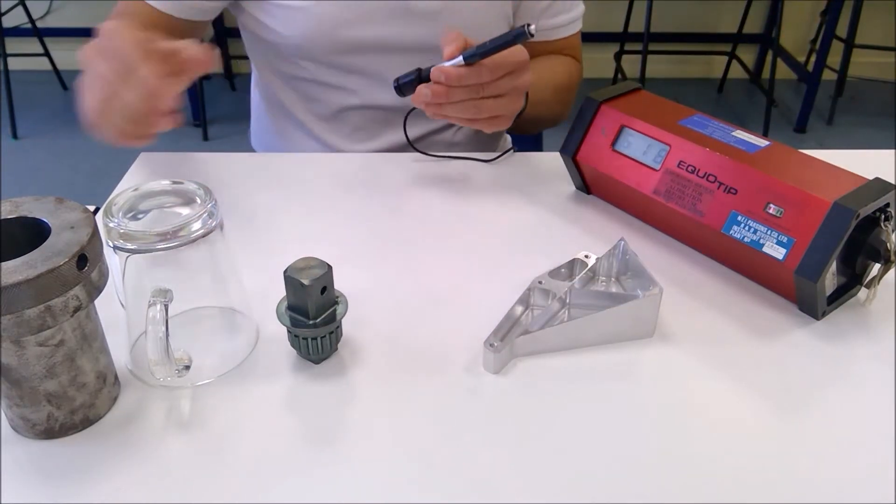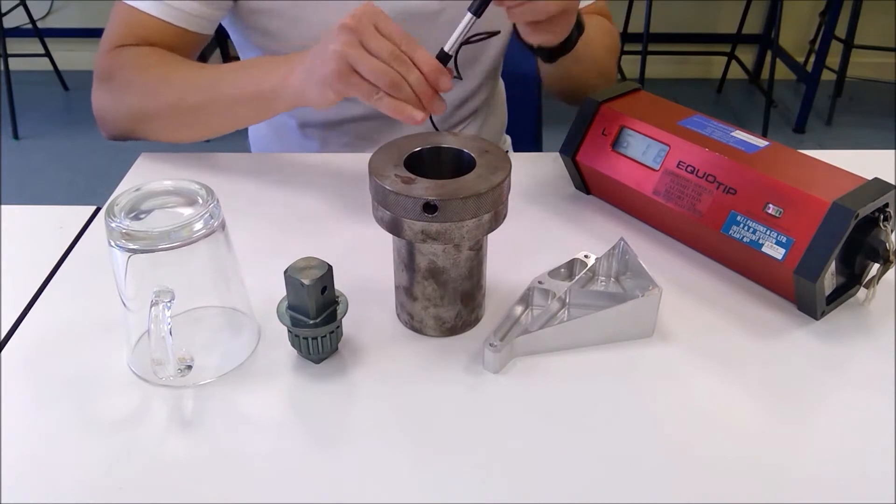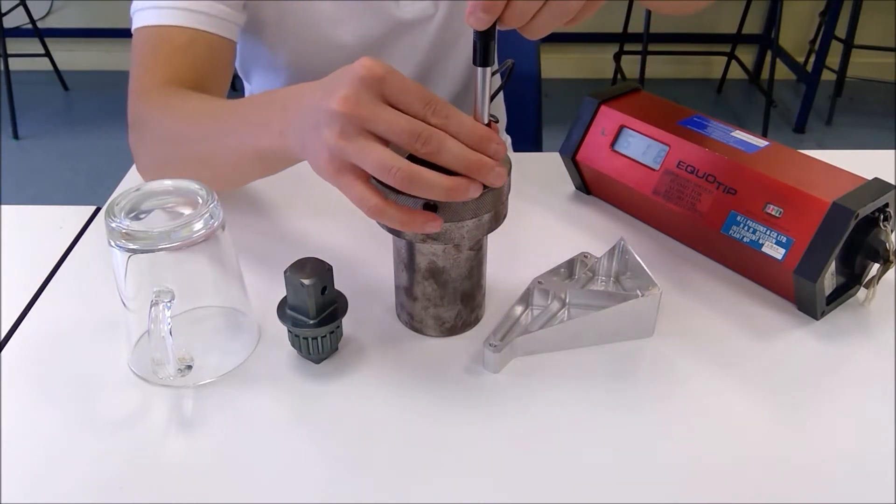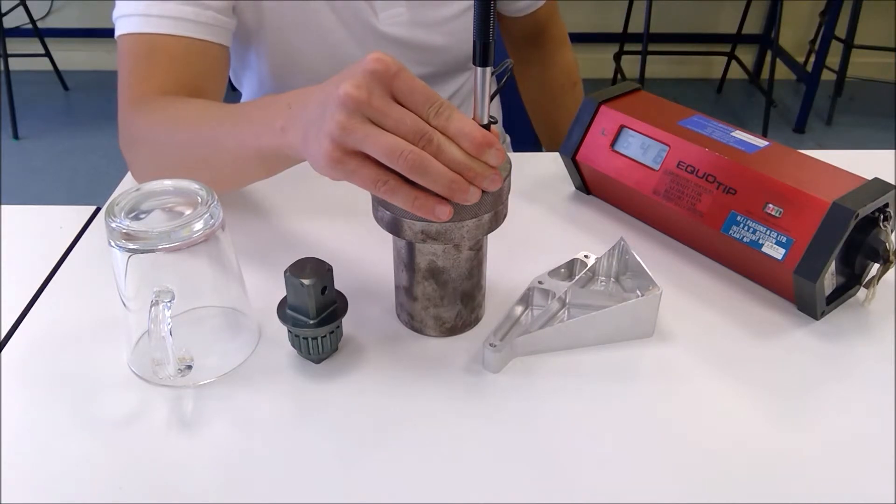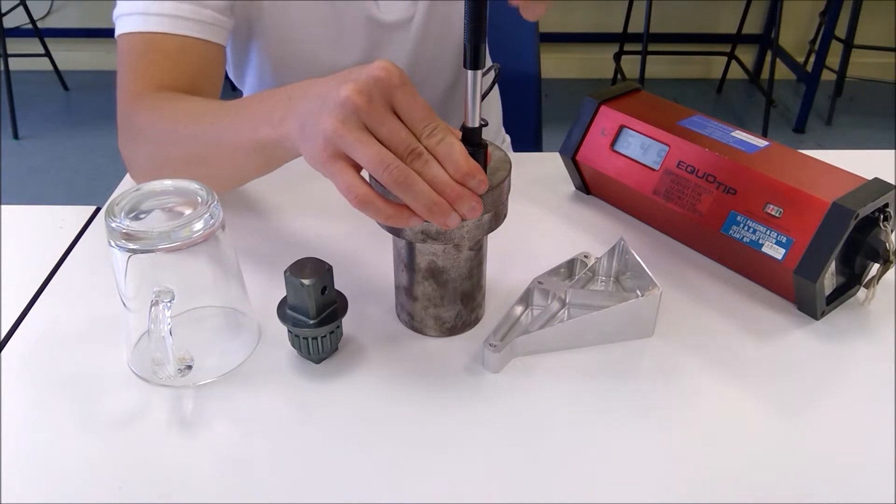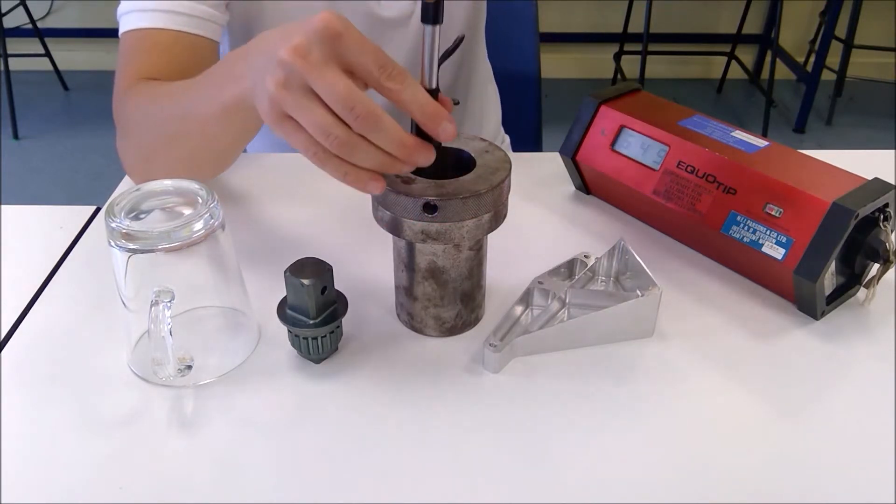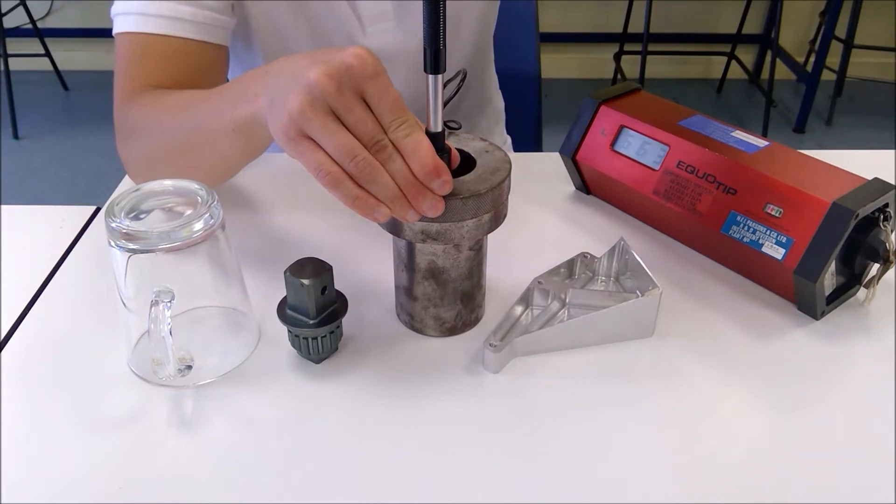Let's move on to our second material then and this time we're measuring low carbon steel. Again we retract the collar, place it flat against the surface and release the ball bearing. 646. Our second reading, 649. And our final reading, 663.